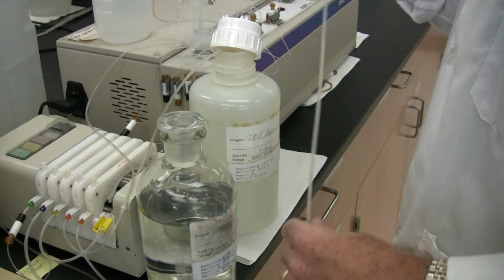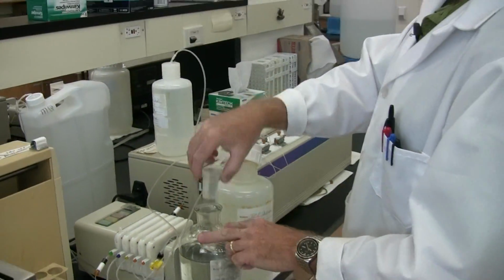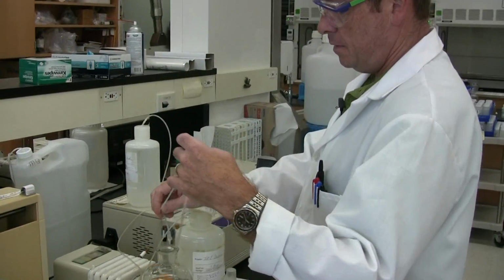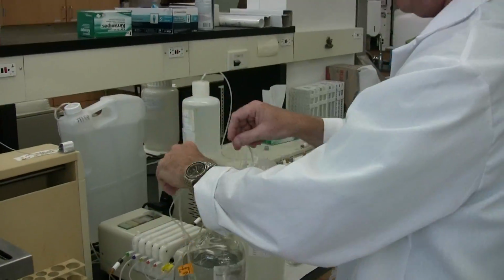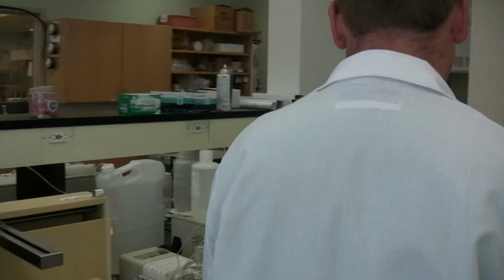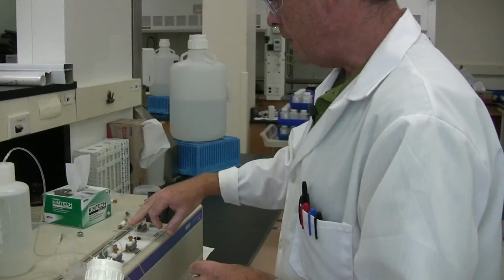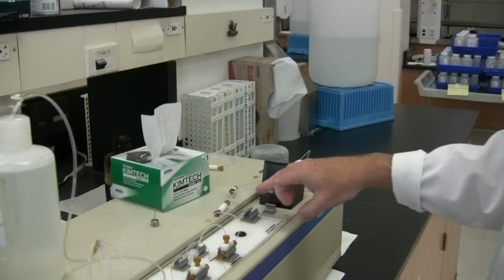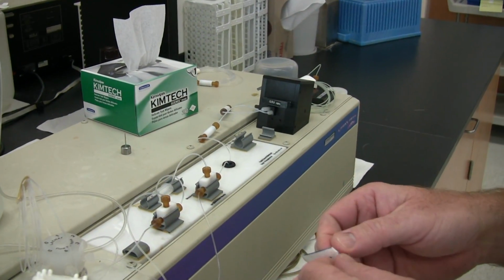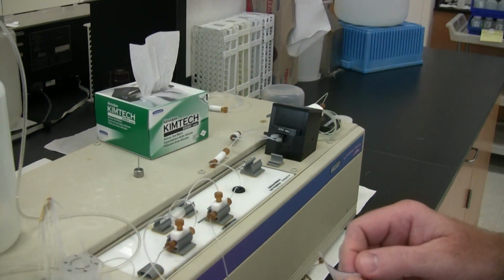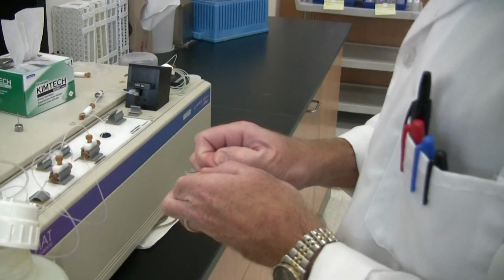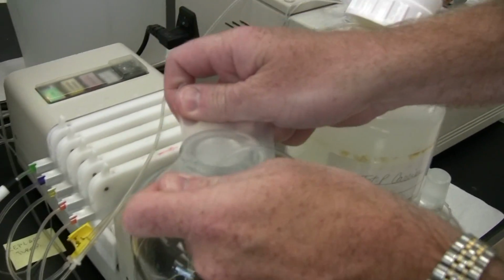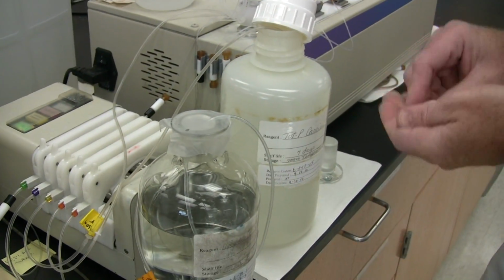And this one goes to the ammonium molybdate, which is the other half of the color reagent. It turns a blue color that's proportional to the amount of phosphorus. Sometimes you can see, if it's going to turn blue, you'll see the blue color before it goes past the flow cell, and the detector detects it. That's just to keep anything from falling in there.